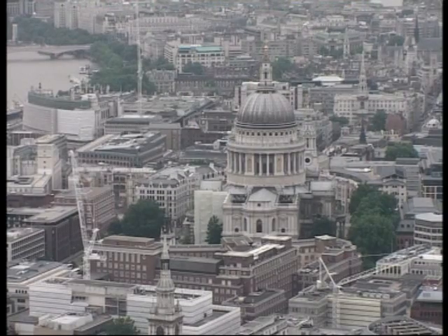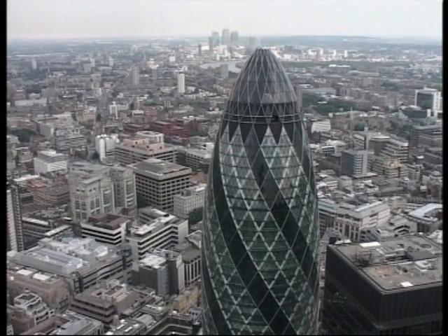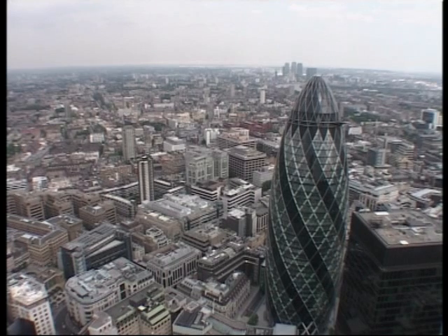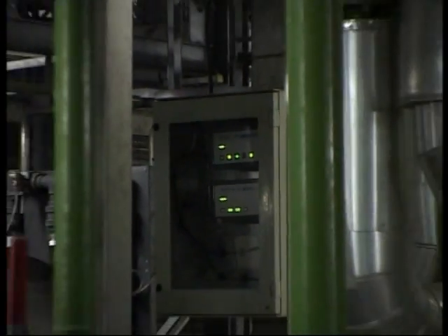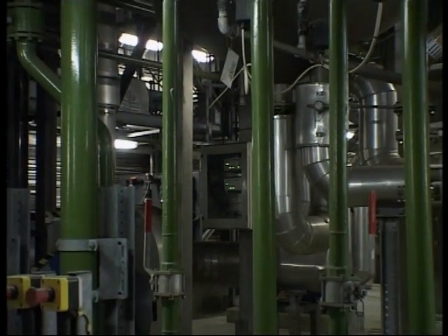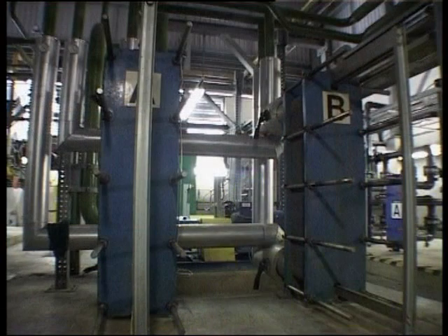From St Paul's Cathedral to the Gherkin, from Southwark Estates to St Thomas's Hospital, ETC is helping more and more institutions to conserve energy and save money. Since having the ENiGMA put into the building, it's taken a lot of effort and hard work from us off. Prior to the system going in, we had to change the heat exchangers every 12 hours, which now we only have to take apart every 2 to 3 months. It only takes about an hour to do so. We're very pleased with that situation.